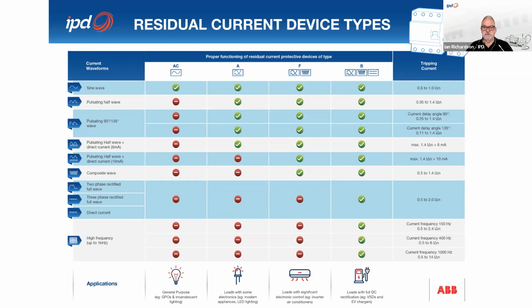We're seeing a lot of single-phase inverter technology, such as air conditioners and some washing machines. This has introduced a high-frequency element to potential earth faults. To detect this, a relatively new product called a type F was developed, which does everything a type A can do, but can also detect earth faults with frequencies up to 1000 hertz. Where we have loads that provide a full DC rectification, things like a variable speed drive or an EV charger, which are becoming quite popular, a pure DC residual current fault, as well as a high frequency fault, can be seen. So an additional model called a type B was developed. This is capable of detecting pure DC faults, as well as frequencies up to 2 kilohertz. Sometimes we call that the universal type.